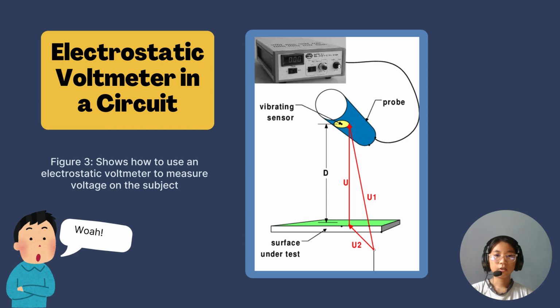Alright, electrostatic voltmeter in a circuit. Figure 3 shows how to use an electrostatic voltmeter to measure voltage on the subject. As usual, we take the voltmeter, connect the probe, calibrate it, and put the probe perpendicular to the surface under test. If it detects the voltage, the movable plate will move, and therefore the voltage is measured.